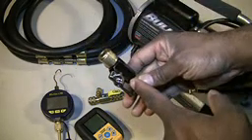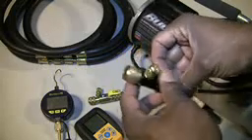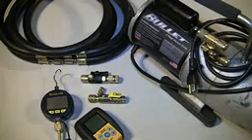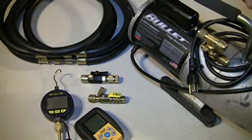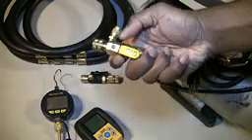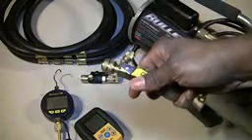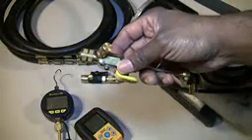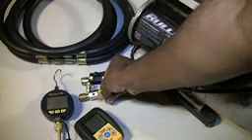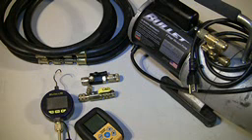The Appion core removal tools — I bought these and the hoses from Trutech Tools. I also bought the gasket sets for these, so it's highly recommended to replace your gaskets once a year so you don't have any issues. Recently I bought the CND core removal tool. I bought some other products and materials to get ready for the coming AC season, and after looking at a couple of YouTube videos I said, why not give CND a chance? The last job I used it on — an air handler install — they worked fine and allowed me to pump down to 500 microns.